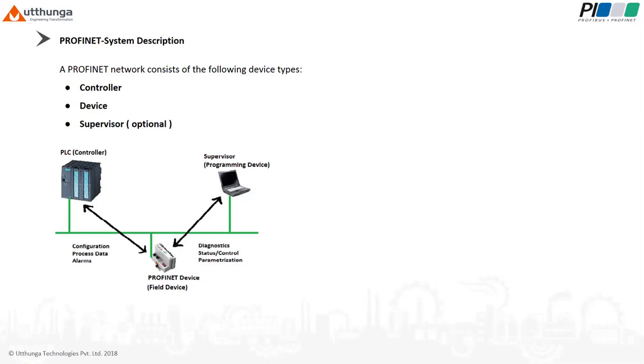A plant unit should always contain at least one controller and one or more devices. Supervisors are usually integrated only temporarily for commissioning or troubleshooting purposes, like for some diagnostics or any plant checkup purposes; we will be using supervisors. From the image, it's very clear who is the supervisor, who is the controller, and the device. The controller and device will be exchanging configuration data, process data, and alarms data, while the supervisor and the field device, the PROFINET device, will be exchanging diagnostics data, status or control data, and parameterization data only during troubleshooting or commissioning, since the supervisor is optional.